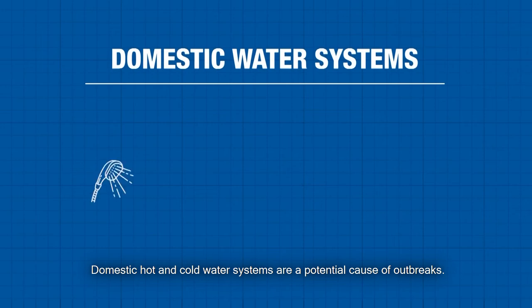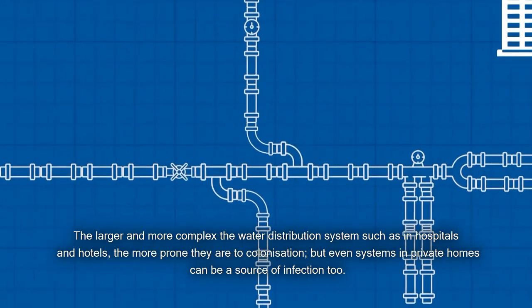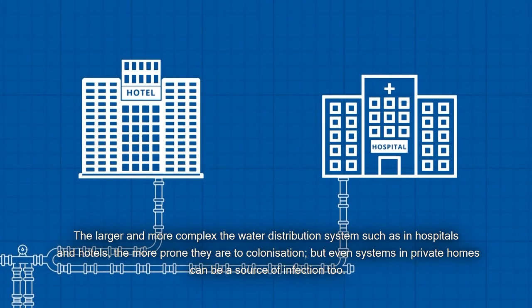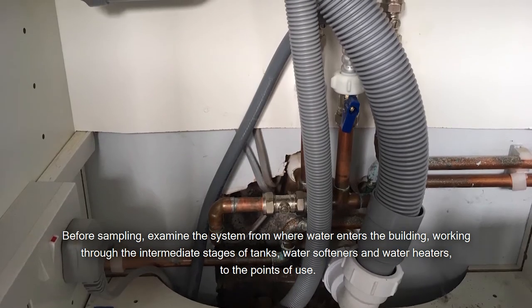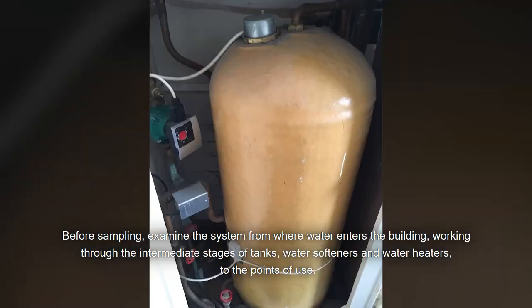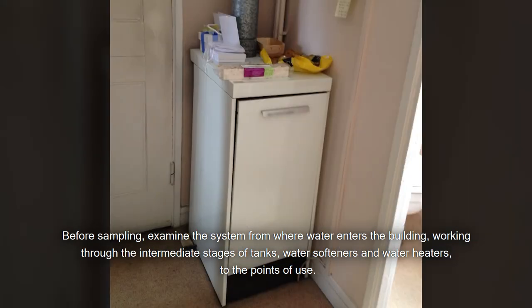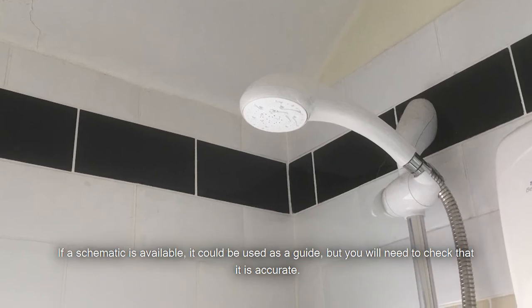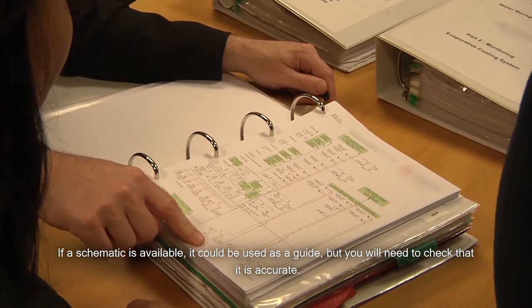Domestic hot and cold water systems are a potential cause of outbreaks. The larger and more complex the water distribution system, such as in hospitals and hotels, the more prone they are to colonisation. But even systems in private homes can be a source of infection too. Before sampling, examine the system from where water enters the building, working through the intermediate stages of tanks, water softeners and water heaters to the points of use. If a schematic is available, it could be used as a guide, but you will need to check that it is accurate.